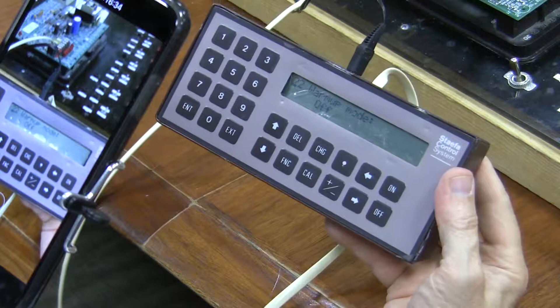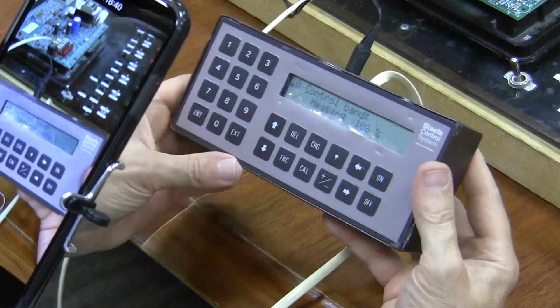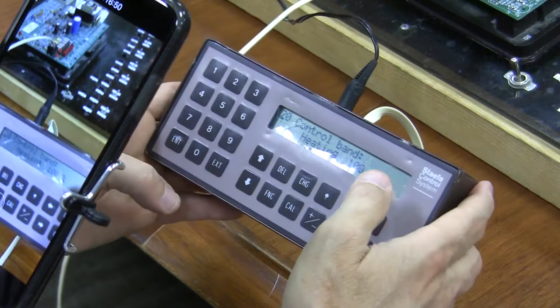Now, what if I wanted to actually just say, card, I want you to just go to 100% cooling. I can't change it right there at the Control band parameter because there's no CHG there. Of course, there wouldn't be unless I'm in function mode in commissioning mode, which I think I disconnected. So let's just make sure we're in commissioning mode.